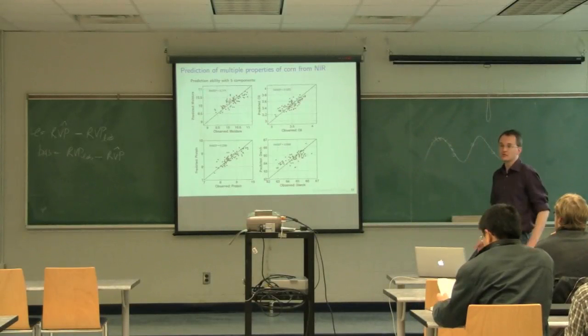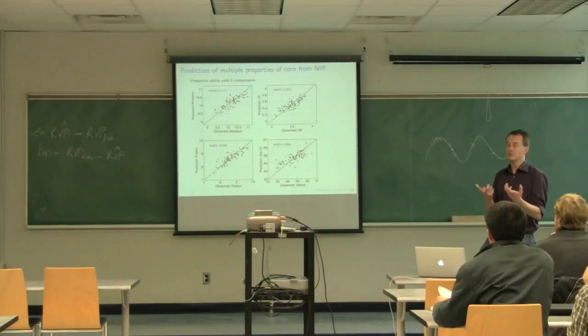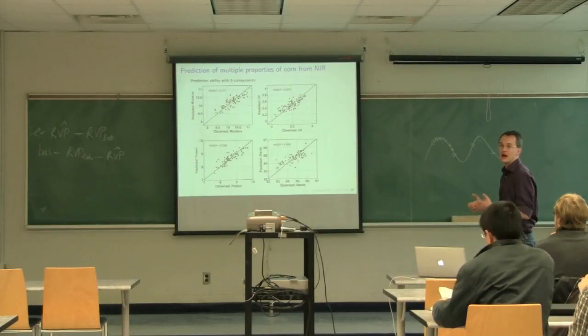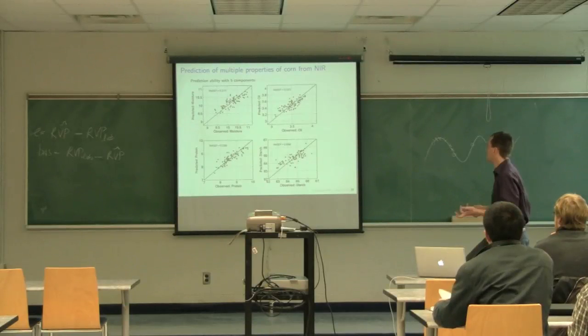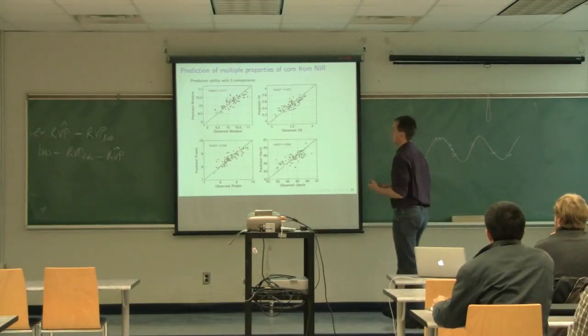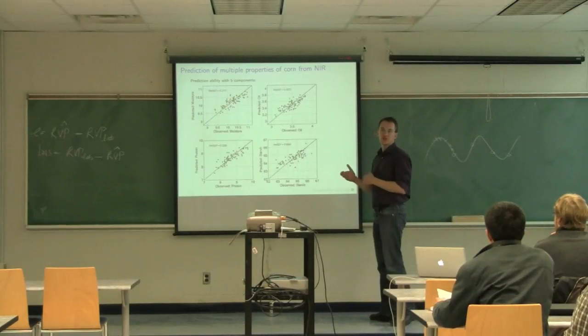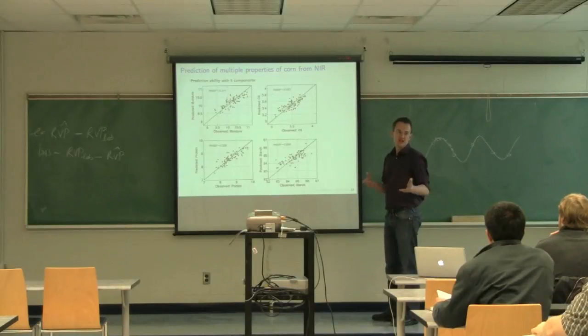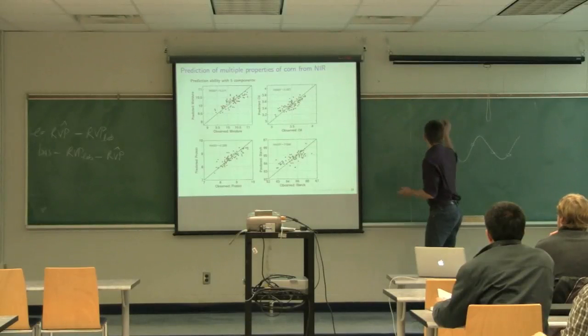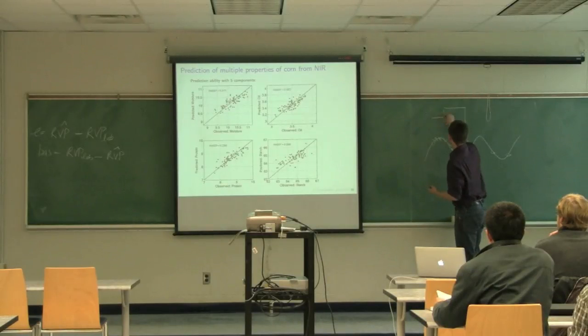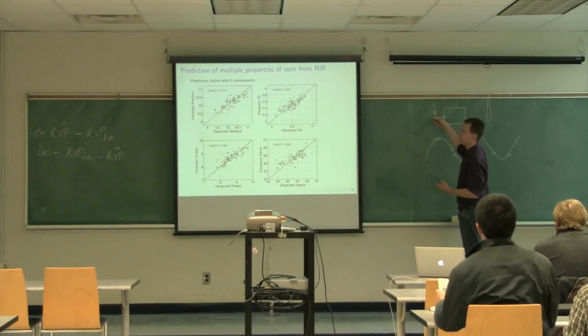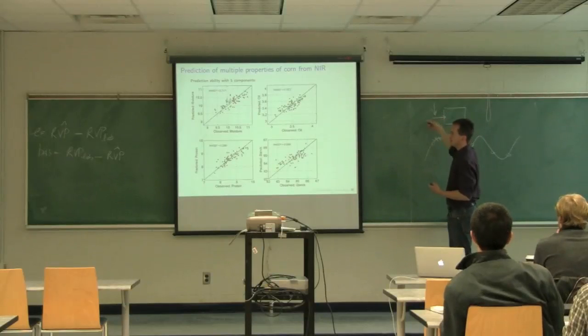So again, this would be great to apply online, because you can then measure the properties of your corn as it's coming in. If you needed to run a process where you know you needed corn with a certain moisture as the input to the process, you could have your process line and the input, and you have a near-infrared probe just looking at the input stream over here, predicting what the value of moisture is.